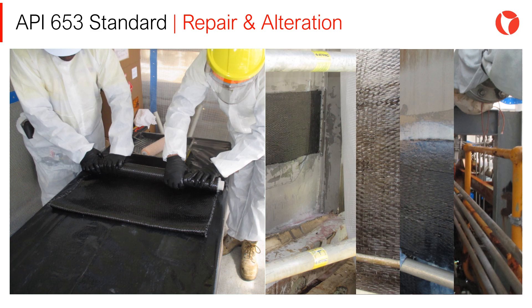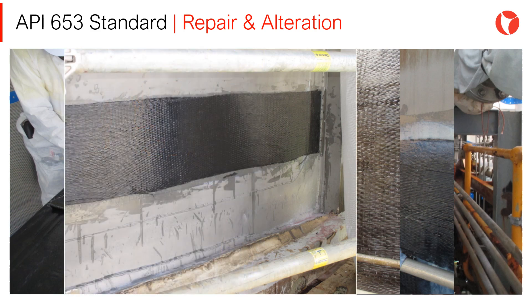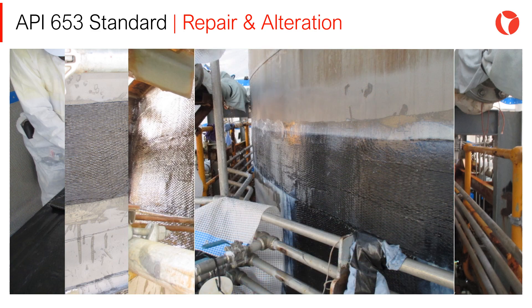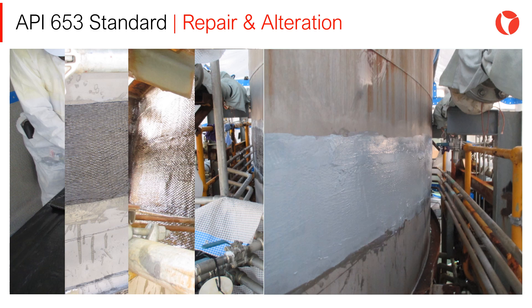An example of a repair using non-metallic materials is shown on the screen. First, the non-metallic or composite material is prepared. Once the composite element is prepared, it is attached and glued to the tank shell by means of epoxy and other resins. Once the composite patch is added to the shell, it is painted and several layers of resins and other gluing materials are added. Finally, it is lined and covered with special paint to ensure that the repair will last as required.